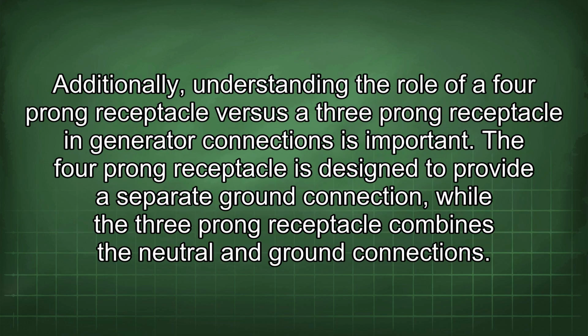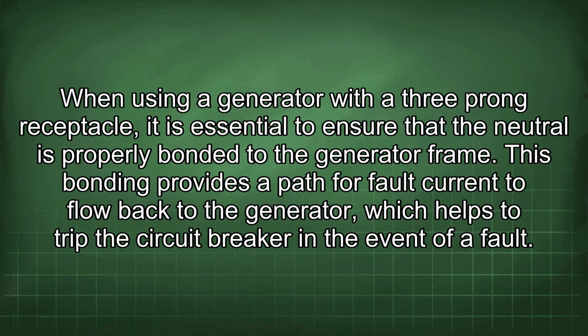Additionally, understanding the role of a 4-prong receptacle versus a 3-prong receptacle in generator connections is important. The 4-prong receptacle is designed to provide a separate ground connection, while the 3-prong receptacle combines the neutral and ground connections. When using a generator with a 3-prong receptacle, it is essential to ensure that the neutral is properly bonded to the generator frame. This bonding provides a path for fault current to flow back to the generator, which helps to trip the circuit breaker in the event of a fault.